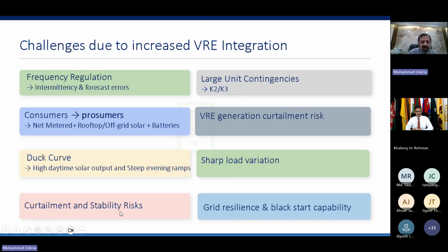Curtailment and stability risk - yes, stability risk again, high voltages over the system, because as already said we have a 7,000 kilometer transmission network, and in low demand scenarios, the network generates reactive power and high voltage itself. I am talking about the primary network of the system. At the distribution level, DISCOs are also facing reverse power flow, network overloading, and voltage issues on their 11 kV and 132 kV transformers. But these all come up as a whole to the primary transmission network.